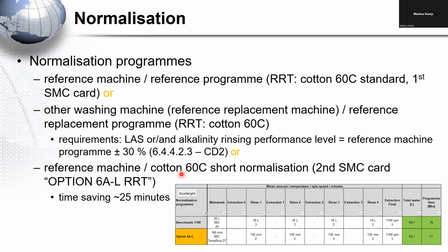And with this short normalization program, you have a time saving of about 25 minutes. It's on the second memory card, and it's called option 6A-L RRT. And the difference between the standard reference program, which is called here in this table benchmark 1100, and this short normalization program, option 6A-L, is a time saving of around 25 minutes, as said before, but the water volume is a little bit different too, because it was changed from filling by weight to filling by level. But in our tests we have done here, we guarantee that the rinsing performance of this short normalization program is the same as in the reference program.